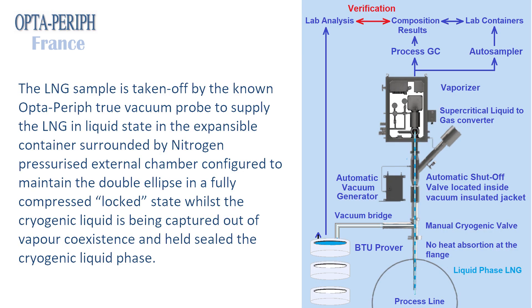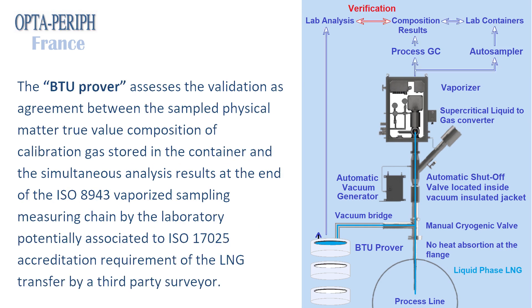The LNG sample is taken off by the known Opta-Periph True Vacuum Probe to supply the LNG in liquid state in the expansible container, surrounded by nitrogen pressurized external chamber configured to maintain the double ellipse in a fully compressed locked state, whilst the cryogenic liquid is being captured out of vapor coexistence and held sealed in the cryogenic liquid phase. The BTU Prover assesses the validation as agreement between the sampled physical matter true value composition of calibration gas stored in the container and the simultaneous analysis results at the end of the ISO 8943 vaporized sampling measuring chain by the laboratory, potentially associated to ISO 17025 accreditation requirement of the LNG transfer by a third-party surveyor.